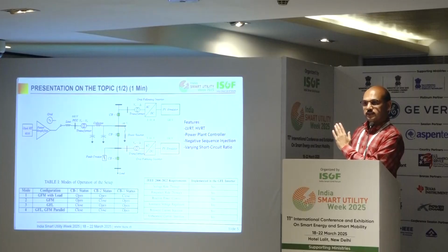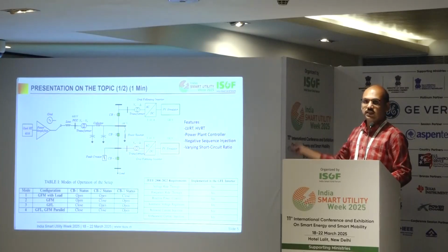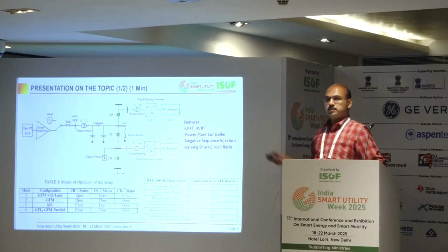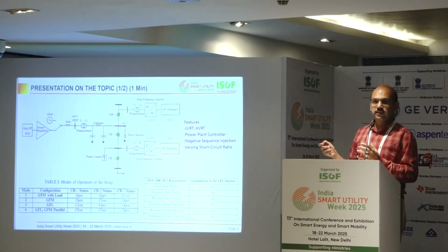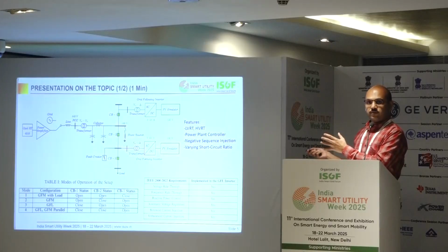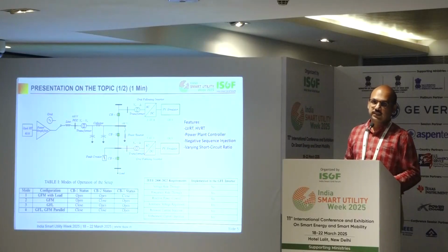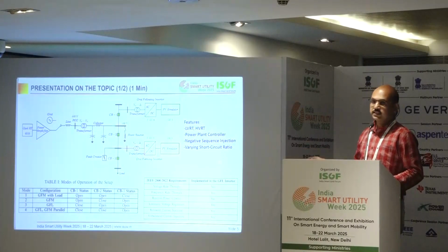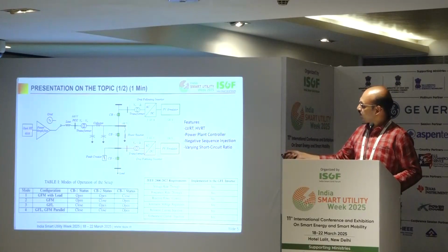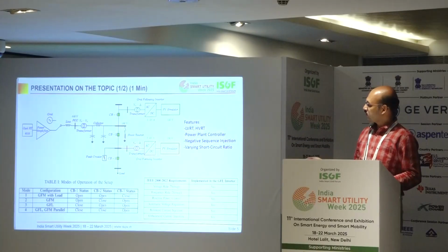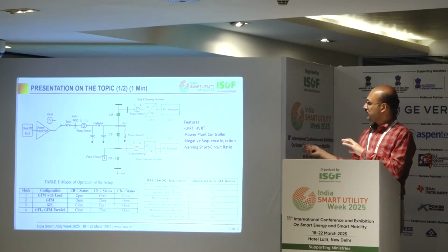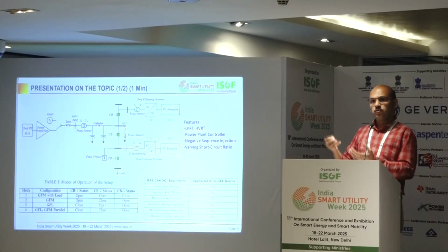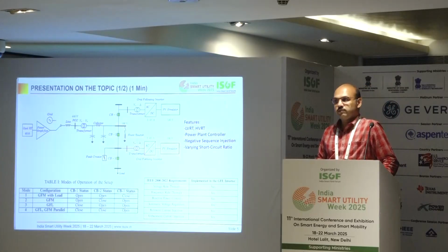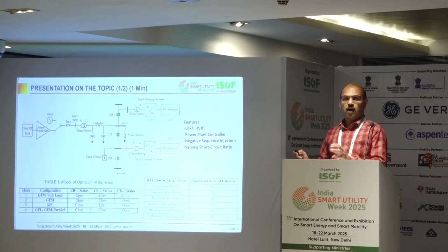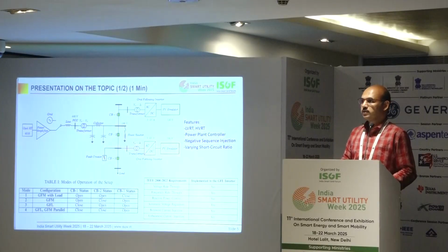Then you take out one bus and you connect your physical inverter plant to that bus. So it will give you a feeling of how this plant can behave if it is connected to a real power system. And you can scale it up. Even though it is 6 kVA, when we are simulating inside the simulator, we are scaling it up, so we can have 150 megawatt. So inside the simulator, we are scaling to a 150 megawatt power plant. This gives you a lot of flexibility to study how an exact physical plant will behave when connected to any particular part of the power system.